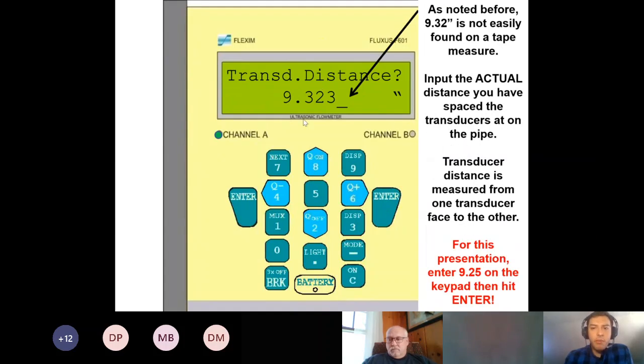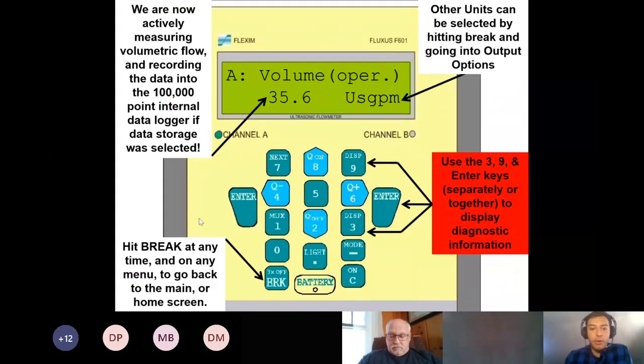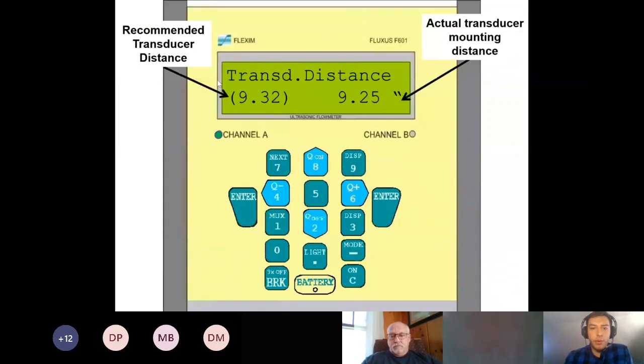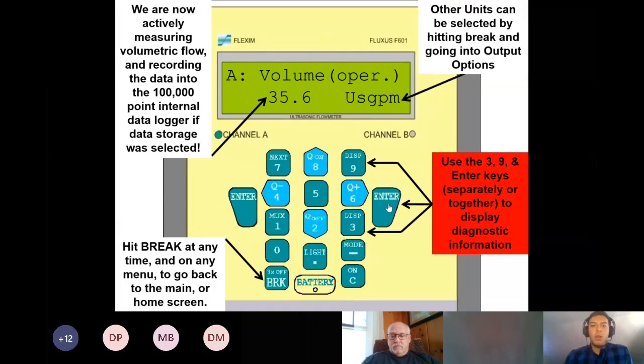This is the menu I was saying before, where you can manually type in the spacing for your transducers. So instead of doing 9.32, we can actually type 9.25, and it'll tell us right there, this is the recommended distance, and then this is the actual spacing that we did. All it's doing is changing the reflective angle of the transducers. And then once you hit enter one more time, you should be reading. You see here your gallons per minute.